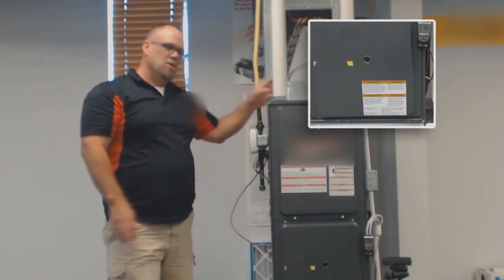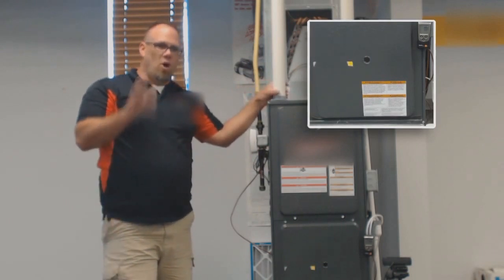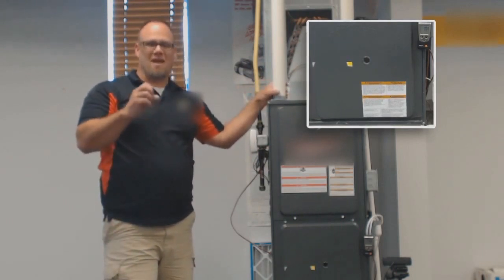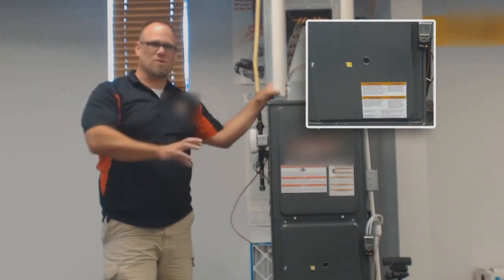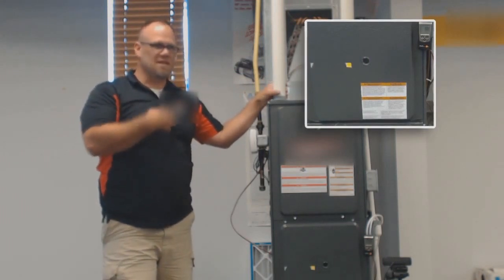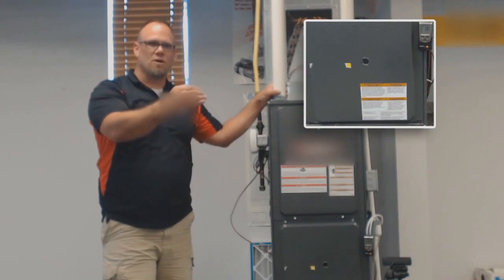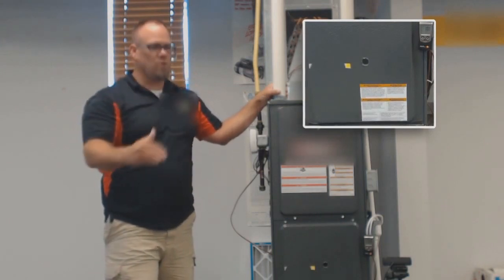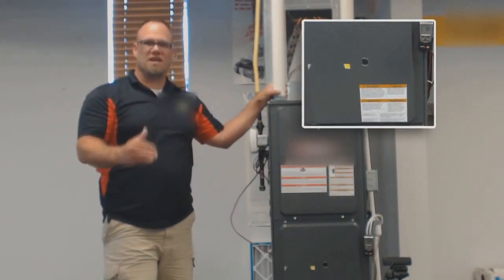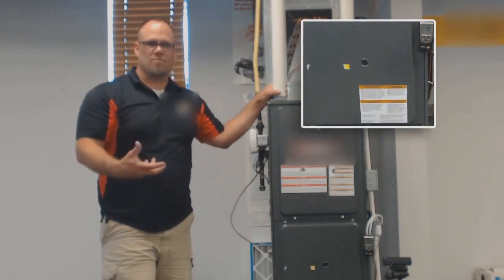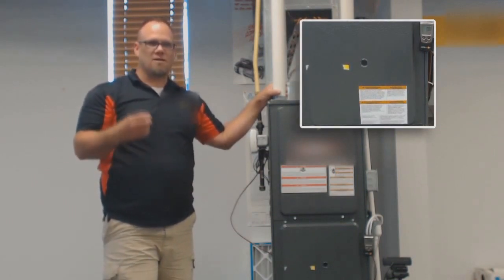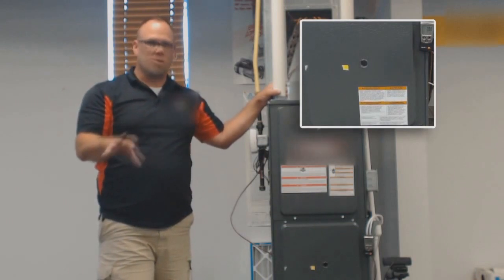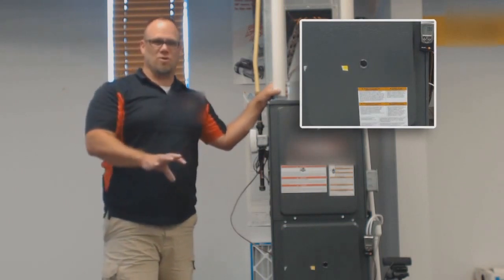Now, traditionally, we have always been told or have assumed, some of the old school guys like myself, it comes on high from the manufacturer for air conditioning speed. It comes on low from the manufacturer for heating speed. We just leave it there. And that's not the way that we are supposed to do it. It's not the way we're ever supposed to do it.